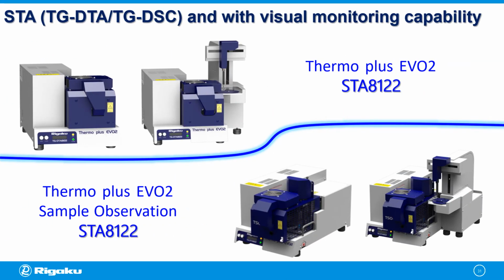Before we move on to our next application, I would like to introduce to you our sample observation attachment for STA. Existing customers with Thermo plus EVO2 STA8122 equipped with a standard furnace can later purchase the electric furnace with a built-in sample observation unit as an add-on option. With these attachments, the user can easily replace the standard furnace with a sample observation unit.